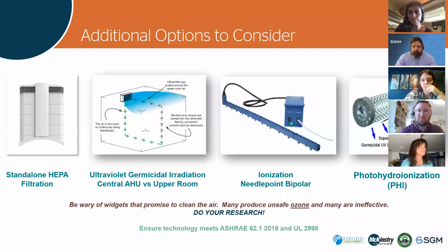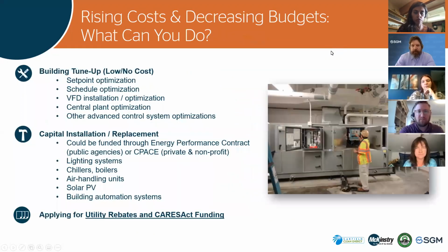Well, like Brian said earlier, with UV, it's really how long can the air stay in the UV path. Needlepoint bipolar ionization is actually putting these ions out in the space. And they actually make some measuring devices now. You can even attach them to your BAS system. So you can measure how much ionization is in your space, and it can have an alarm to BAS to go check items that you've put on your rooftop units if they're not producing enough. Again, it's fairly new, and we don't have a lot of case studies yet to say how effective it is, but as far as new and being implemented, it's not new technology. It's been around for many years. I hope that answered the question.